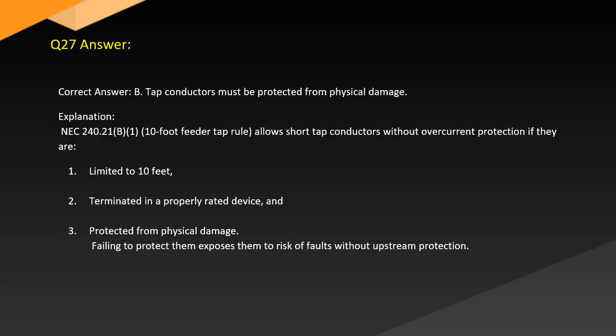Answer. Correct answer: B. Tap conductors must be protected from physical damage. Explanation. The NEC 240.21(B)(1) 10-foot feeder tap rule allows short tap conductors without overcurrent protection if they are limited to 10 feet, terminated in a properly rated device, and protected from physical damage. Failing to protect them exposes them to risk of faults without upstream protection.